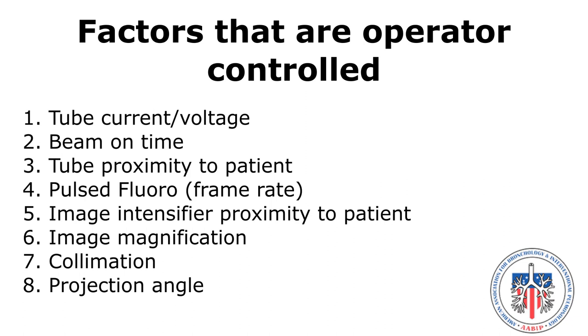Operator-controlled factors include: tube current or voltage, beam on time, tube proximity to the patient, pulsed fluoro or frame rate, image intensifier proximity to the patient, image magnification settings, collimation, and projection angle.